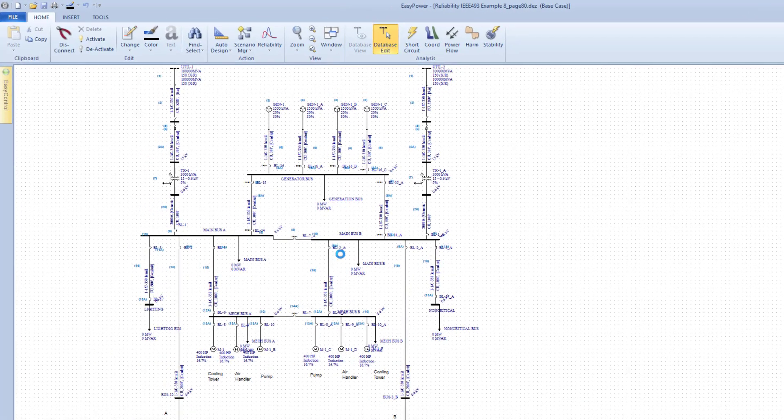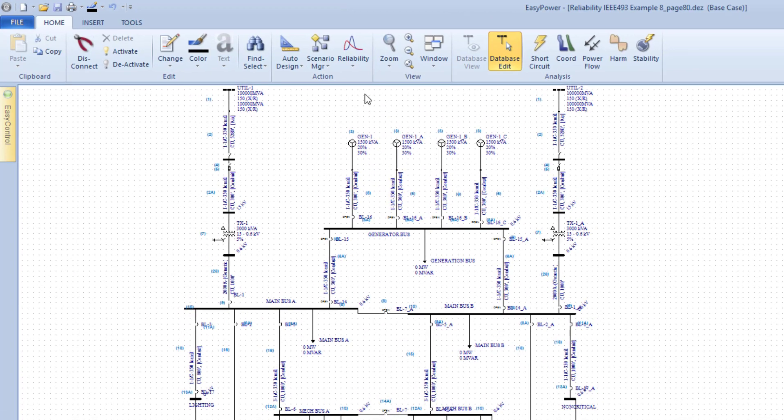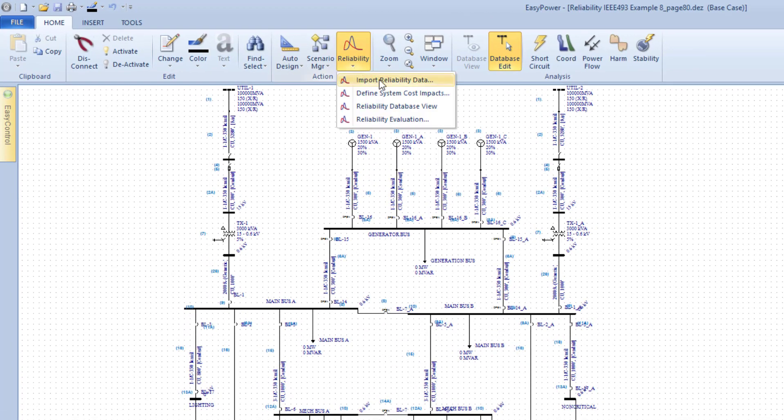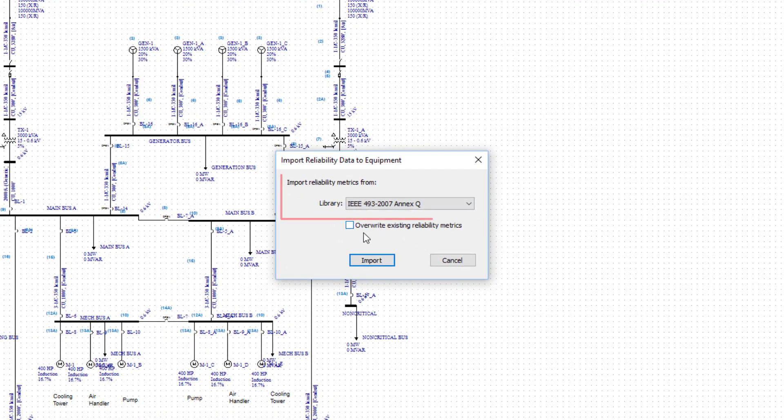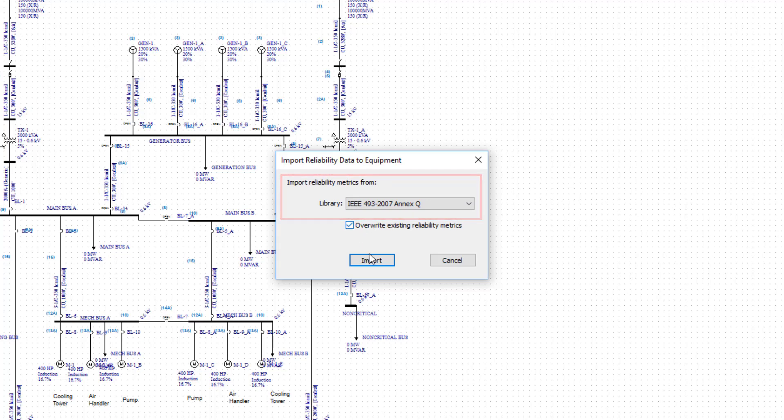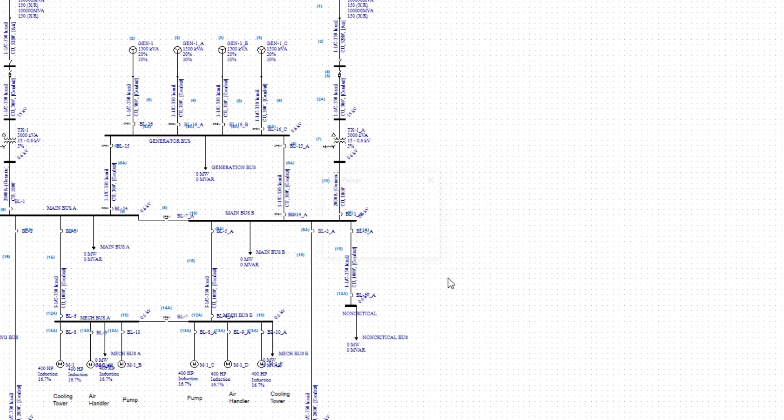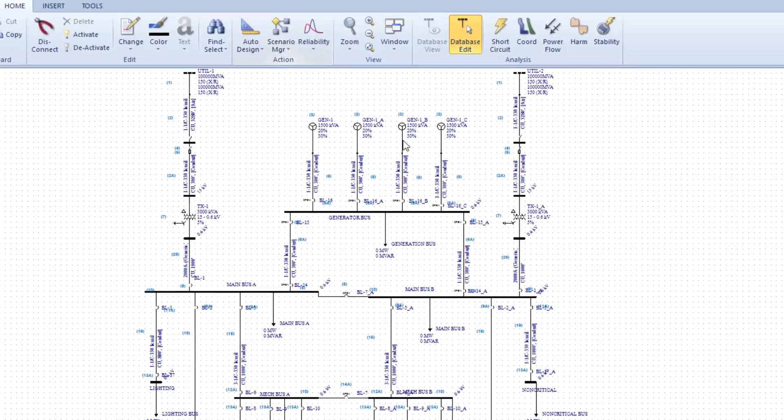Import the Equipment Failure Rate data from Annex Q, which is part of the IEEE 493 standard for recommended practices for the design of reliable power systems. The equipment in the OneLine is updated with the relevant reliability data.